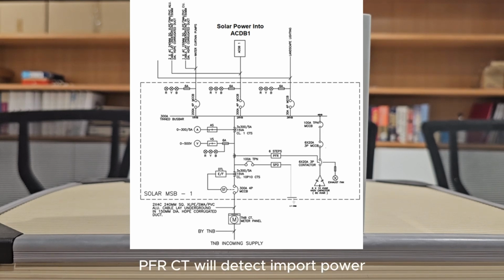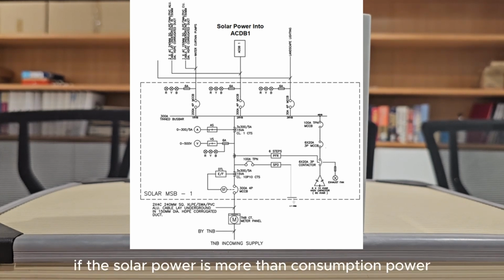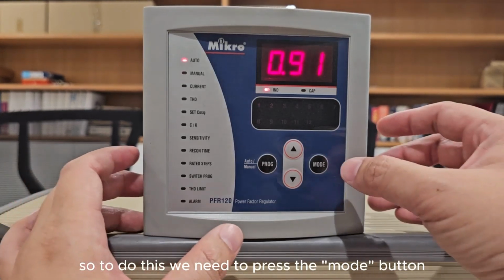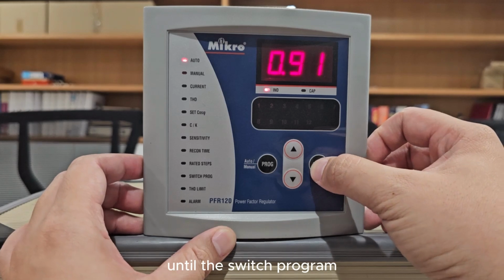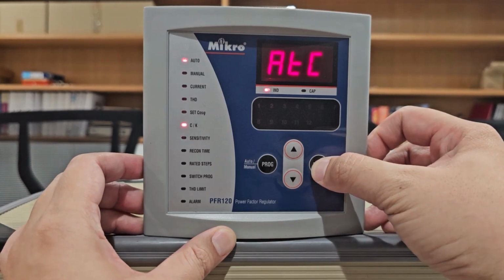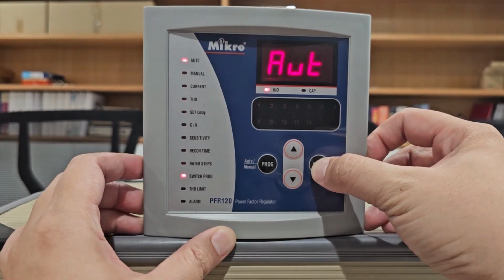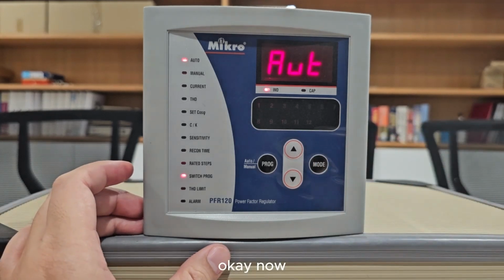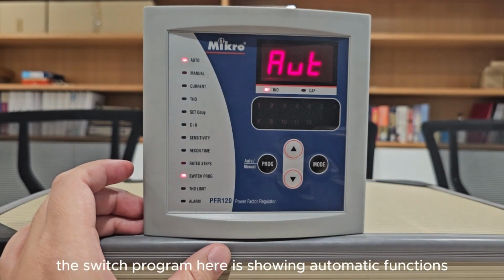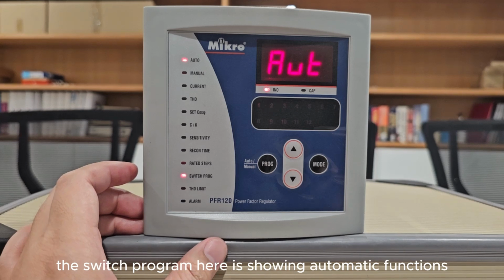PFR CT will detect import power if the solar power is less than consumption power, or it will detect the export power if the solar power is more than the consumption power. So to do this, we need to press the mode button until the switch program. Okay, now the switch program here is showing automatic functions.